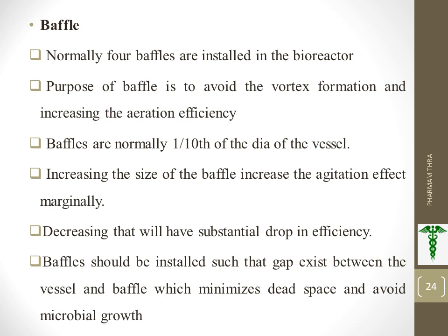Baffles are installed in the bioreactor. Normally, 4 baffles are installed. The purpose of the baffle is to avoid vortex formation and increase the aeration efficiency. Baffles are normally 1 by 10 of the diameter of the vessel.